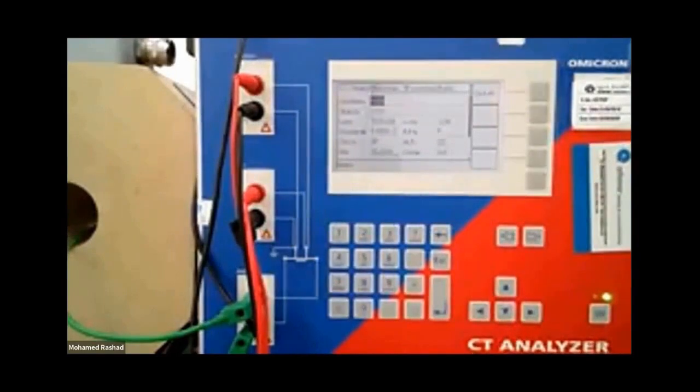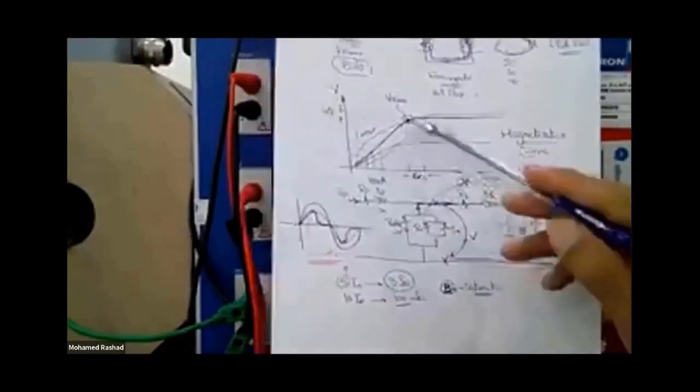As for the excitation curve, well, the matters are simple. Why are things simple? Because you told me yesterday that the matter here is straightforward. Aren't we aware that the more the current increases, its transfer will occur? And when this current transfers and passes through this entire resistance, a voltage is generated here. So the more you increase the primary current, the more the voltage here will increase, until it reaches a saturation point. If the voltage here increases by 10%, the excitation current drawn here in the core itself will increase by 50%.